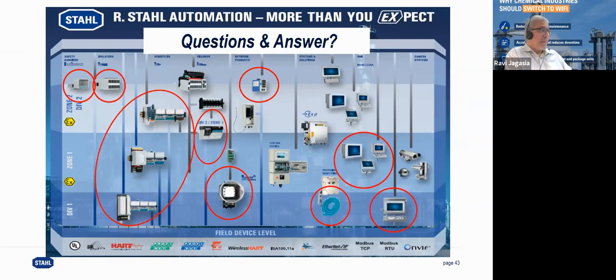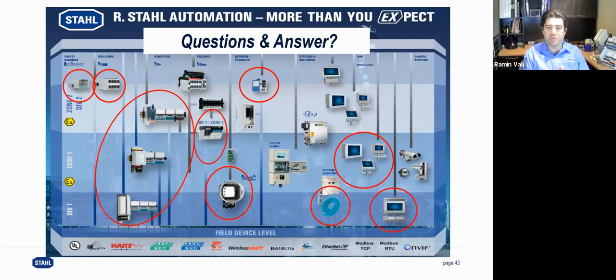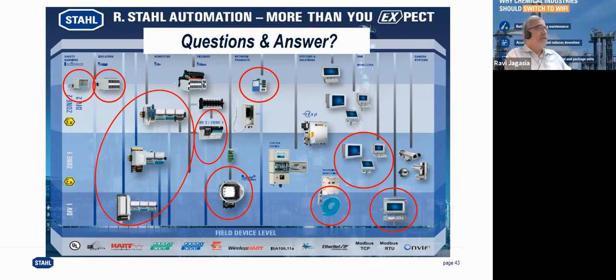Okay, sure. Barbara mentioned that the associated apparatus has 2 circuits. One is to connect to the safe area, and the other one, which was coded in brackets, is to connect to the classified area. So I assume the answer to the question is the circuit which is connected to the safe area is not intrinsically safe. So we can connect it to any field device, any PLC IO card or whatever in the safe area. It's definitely not subject to the classified area restrictions. And the other side, which is the bracket part of the code, can be connected to the field device, which definitely has to be certified as intrinsically safe. I hope we answered your question.